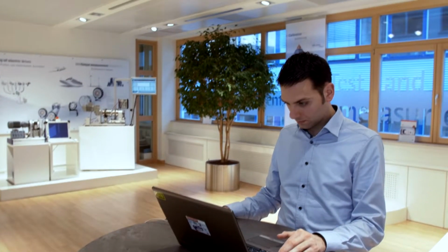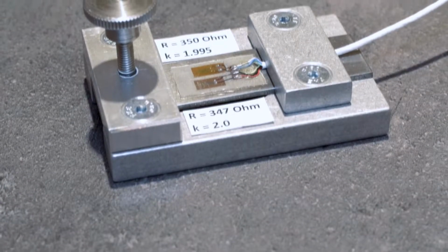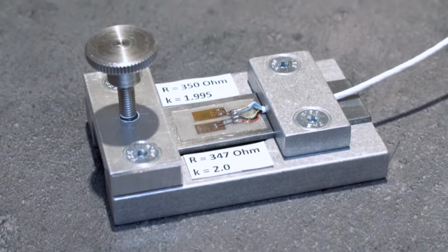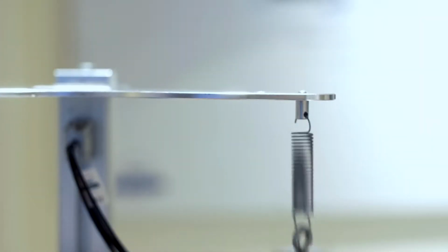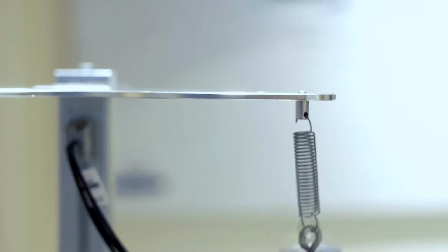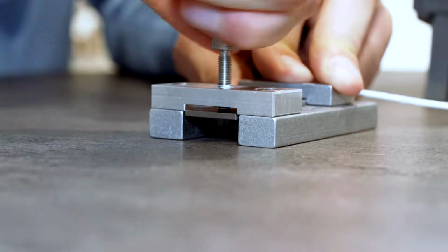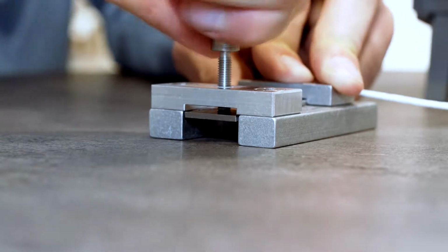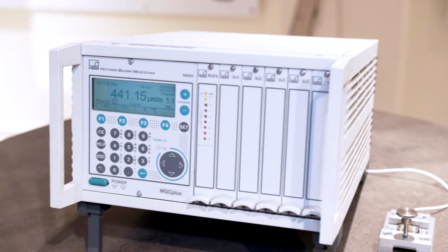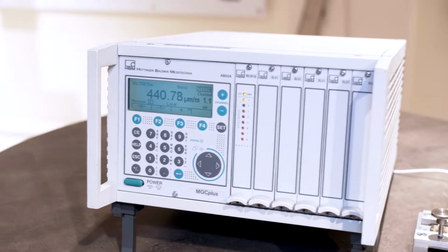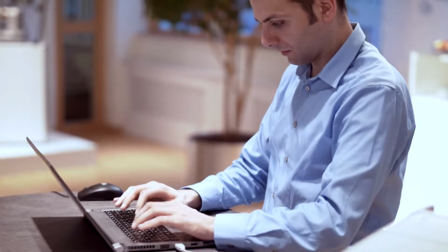Did you know that with strain measurements, the measurement signal needs to cope with two nonlinearities? They are very small and can be neglected in the normally occurring elastic range. These nonlinearities need to be taken into account, however, with extremely high strains. HBM's measuring amplifiers indirectly do so by using a practical effect.